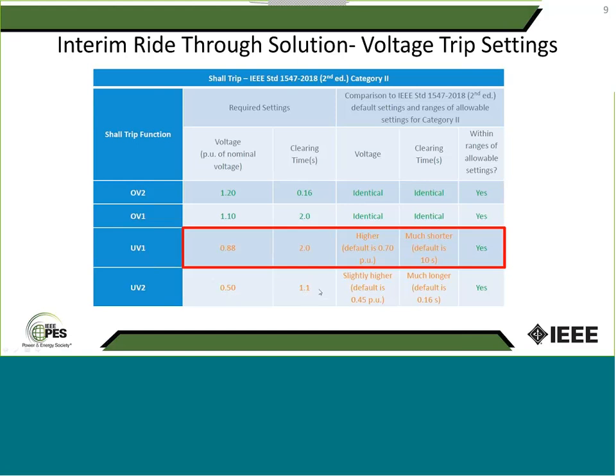The trip clearing time we identified as 1.1 seconds, but the mode that we're mandating is the momentary cessation mode for voltage below 50%. Okay, and what does that mean again? If the voltage goes below that limit, the inverters stop producing current and go to this momentary cessation mode for up to 1.1 seconds. If the voltage recovers within that 1.1 seconds, then the inverters start producing current and the system goes back to normal. But if the momentary cessation mode lasts longer than 1.1 seconds, then the inverters trip.